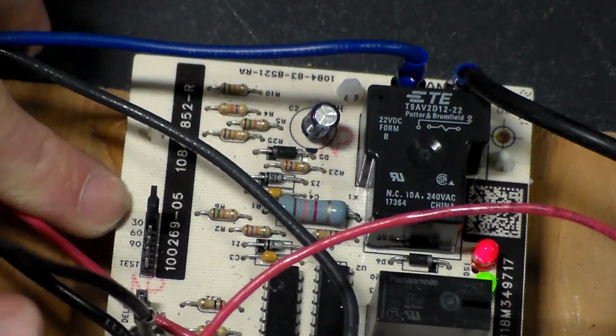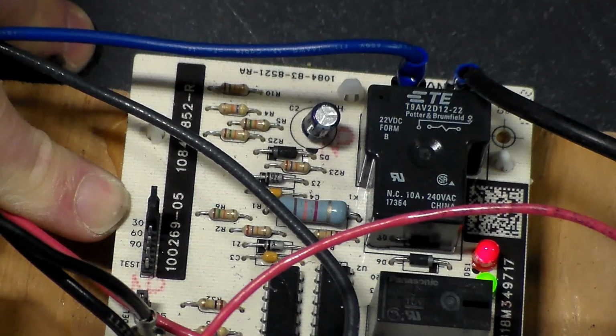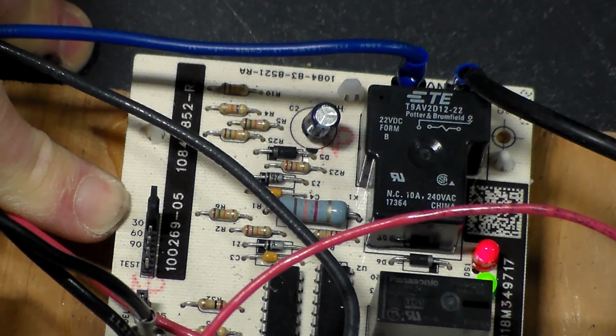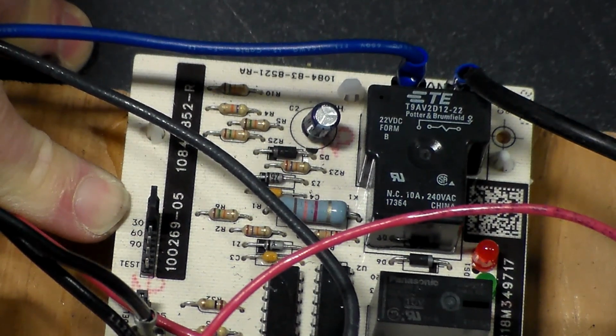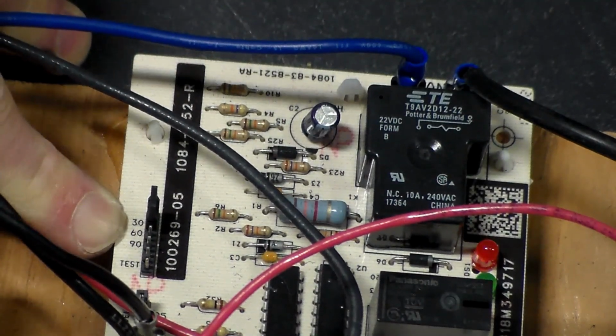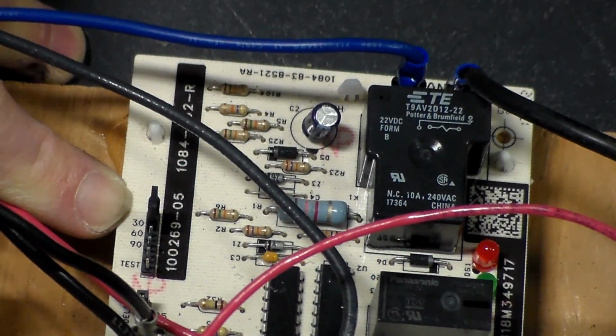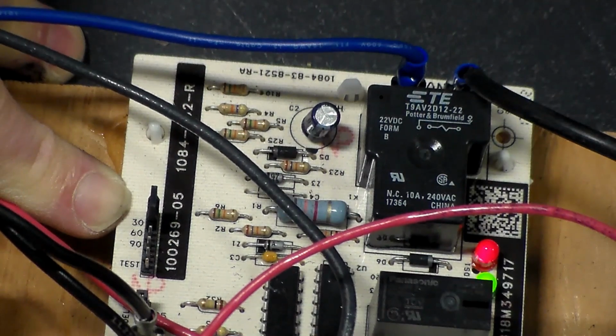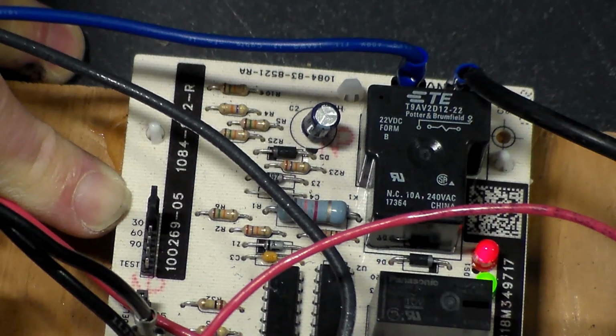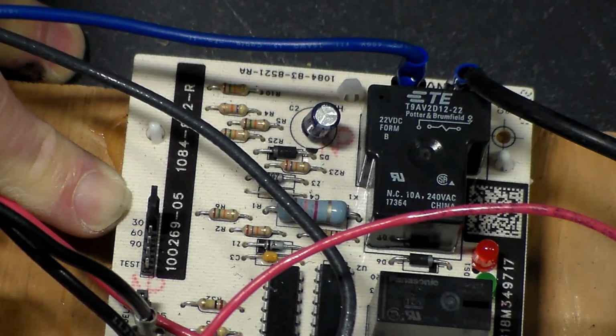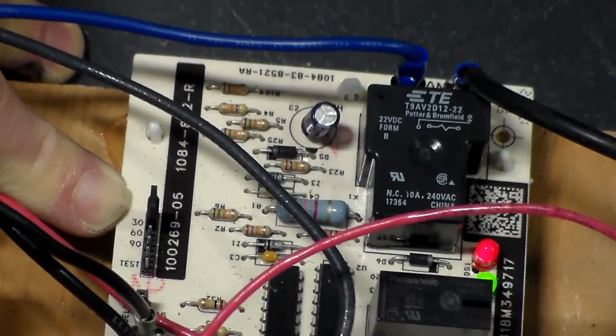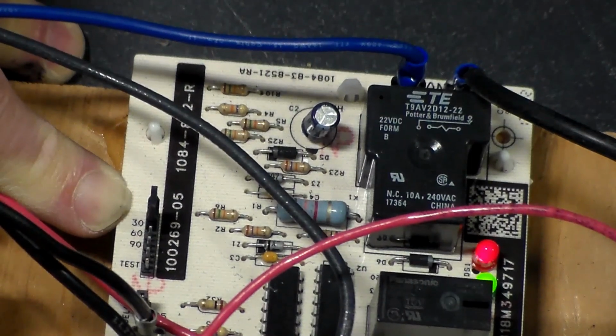What this pin is for is our run time. Here in our area, we have colder winters. It gets lower temps, so we probably want that set for 30. Somewhere milder, we might have 60, and then down south in Florida, we could set it for 90. But what this is, every 30 minutes of run time, it's going to try to defrost. And we talked about that sensor earlier. If the sensor is showing closed or low ohms, then the board is going to go, okay, I'm frozen, I need to defrost. If it's not, the board will shift into defrost, and then within a couple of seconds, it'll kick right back into regular mode again, and it'll start another 30-minute timer.